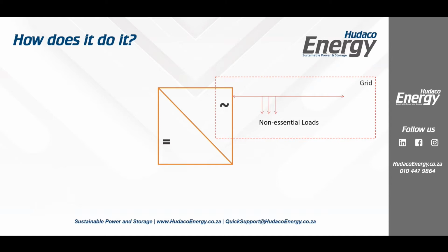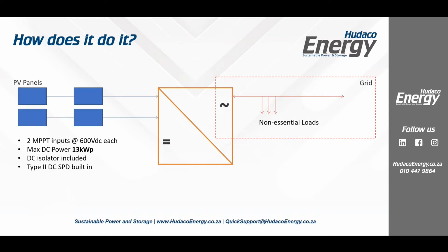The second option is where we connect the PV panels. Those we're going to connect on the DC side. On the PV panels, we've got 2 MPPT inputs on the unit. They are MC4 connectors. You'll see 4 little connectors, or in other words, 2 pairs, male and female, for each of the MPPT inputs. They are 600 volts DC inputs each. The amazing thing about that is it gives us a maximum DC power of 13 kilowatt peak we can feed into the single phase unit, 13 kilowatt peak, which is massive.